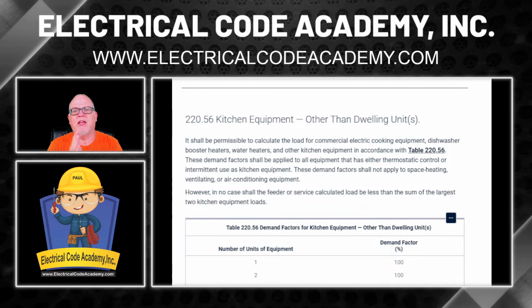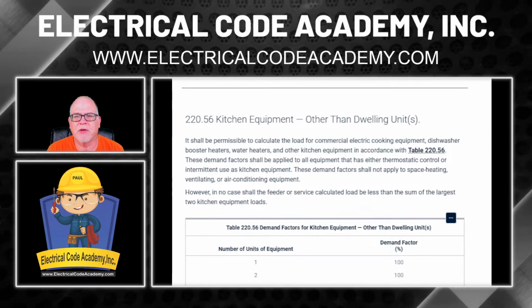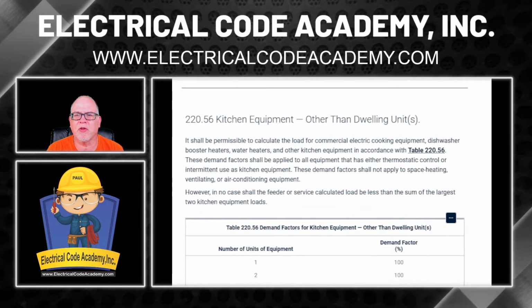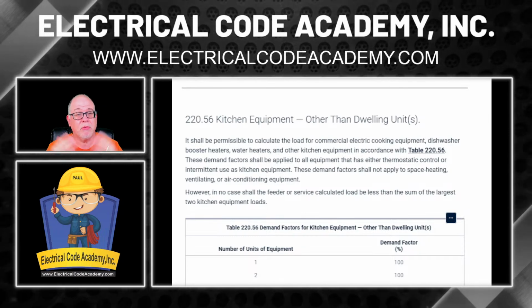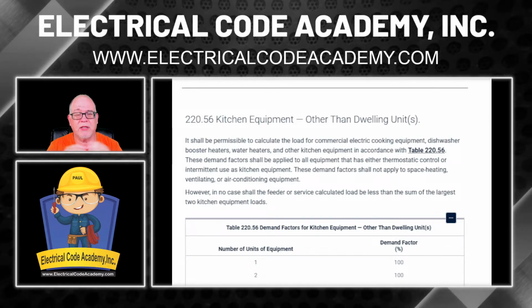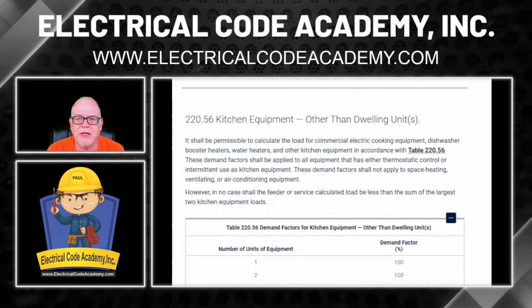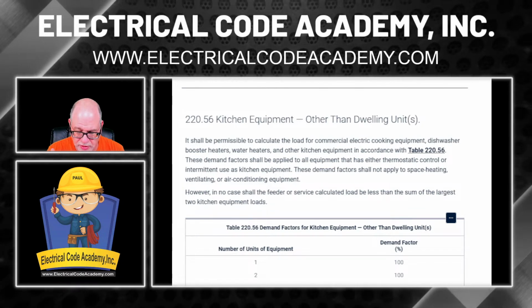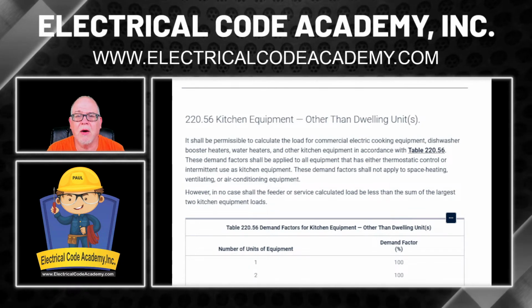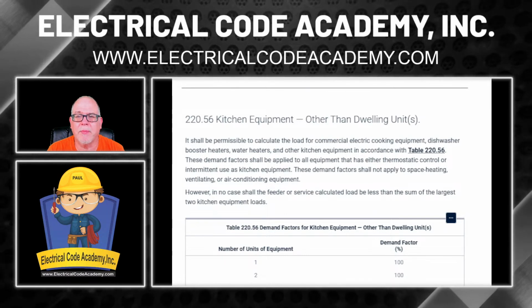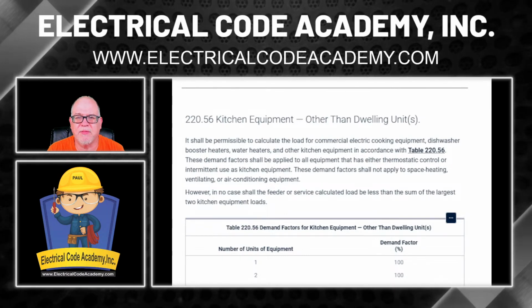All right. So let's read it. It says, it shall be permissible to calculate the load for commercial electric cooking equipment. Okay, so we do have cooking. We have ovens, so we're good there. Dishwasher booster heaters. We do have a booster heater. Water heaters and other kitchen equipment in accordance with table 220.56.